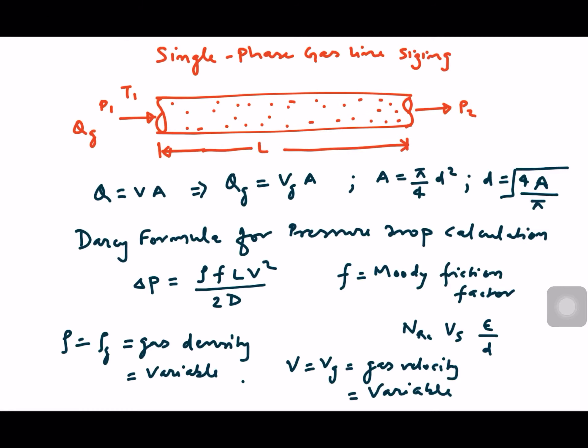Let's talk about the single-phase gas line sizing. We take a pipe of known diameter and length L. When we do gas line sizing, or any line sizing, we first assume a diameter and then validate whether it is correct by checking the velocity criteria and pressure drop criteria for the given flow rates to be carried through this pipeline.